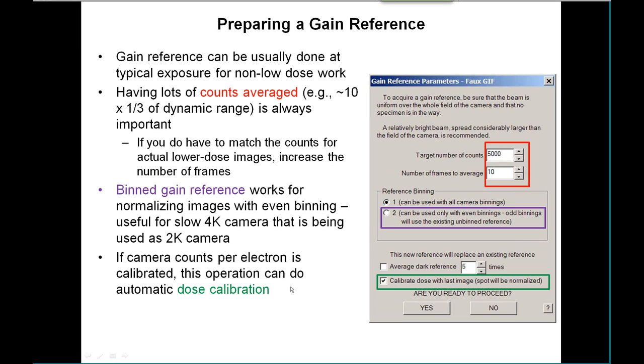Finally, if you have separately calibrated the number of counts per electron that your camera produces and entered that into the property file, then the dose calibration option becomes available and you can calibrate the dose using the last image taken in the GAIN reference.